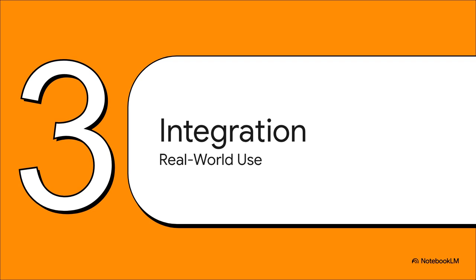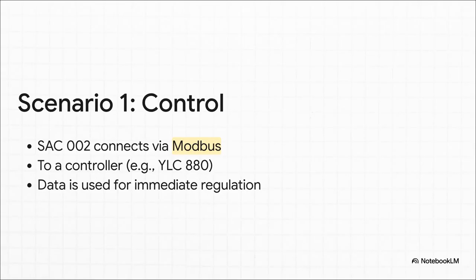So that is a lot of flexibility. But what does it actually look like out in the real world? Well, the datasheet gives us 2 perfect examples of how this chameleon sensor gets put to work in actual building automation systems. Okay, scenario 1, direct control. You'd connect the sensor using Modbus right to a system controller, something like a YLC880. In this setup, its real-time data on temperature, humidity, and CO2 is fed directly to the controller, which uses it to make decisions on the fly, adjusting ventilation, turning on the AC, that kind of thing.